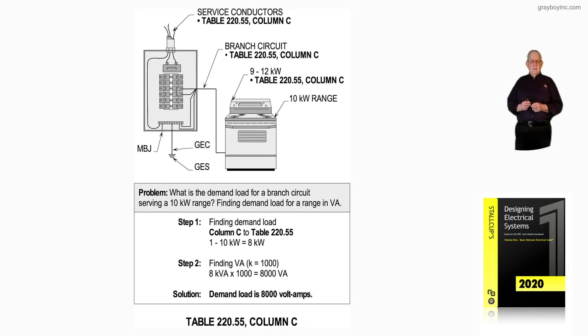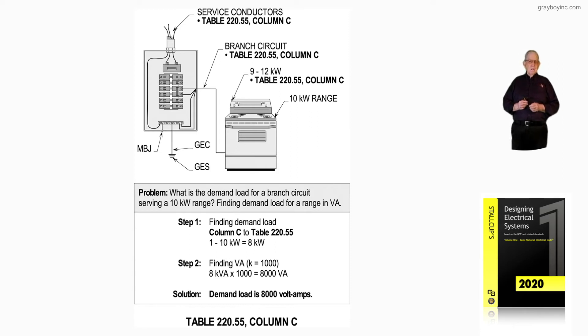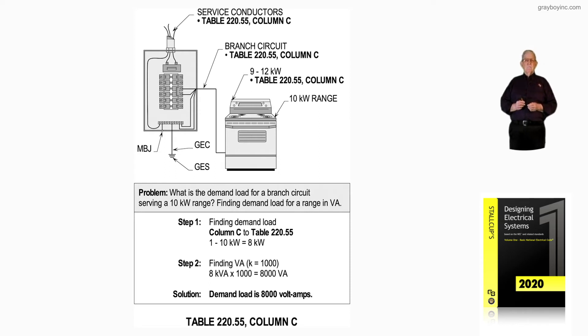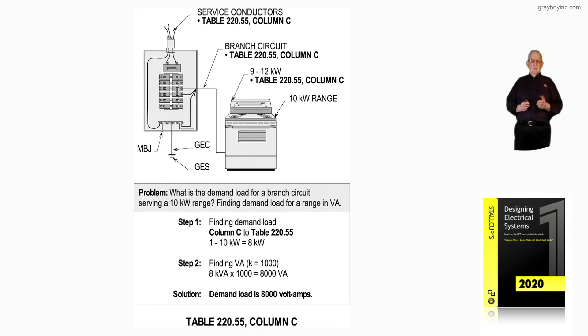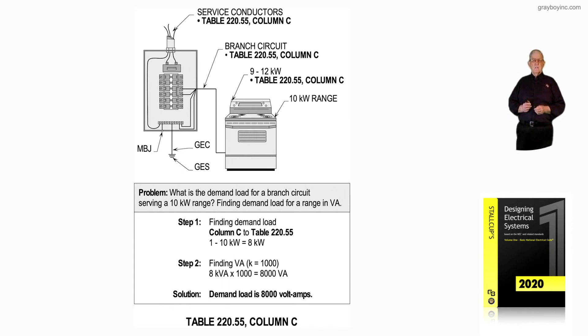Now we're going to get the answer. Step one: we're applying Column C of Table 220.55 for one 10 KW range. There's no math done — it's given to us. It's 8 KW. So step two, we take the 8 KW and express it in volt-amps, as the code does when adding all this up.